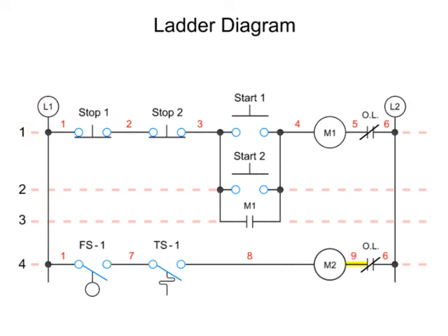Rung reference numbers are usually in parentheses adjacent to the rung in which auxiliary coil contacts and contactors are used. In this schematic, the motor coil on rung 1, M1, is referencing a normally open contact M1. Thus, a 3 in parentheses is placed here.